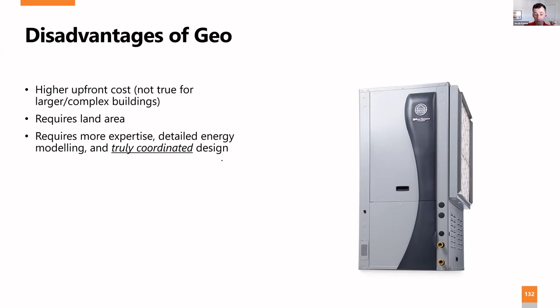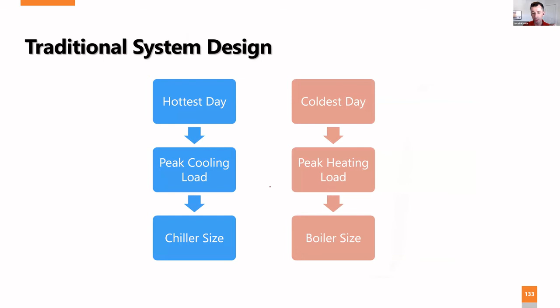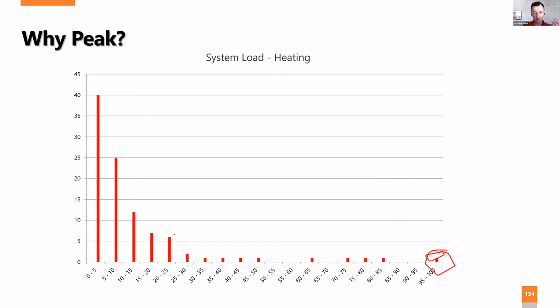You can't just use the peak design days for sizing a geosystem. That peak boiler and chiller sizing is useless for geo design because the energy is not coming from an outside source. With a boiler, as long as you keep paying your gas bill, you keep getting your energy. But that peak almost never happens. Most buildings spend 90% of their life at less than a third of the capacity.